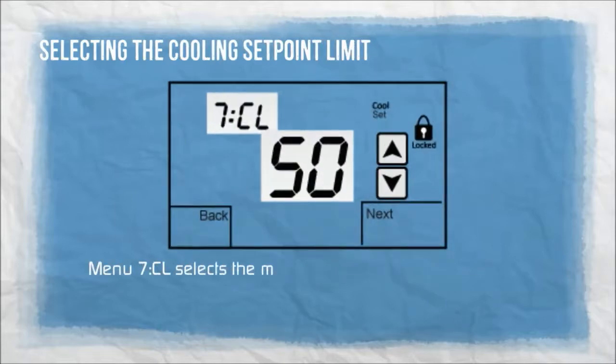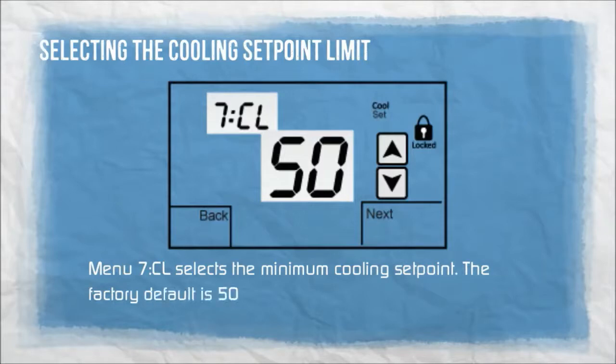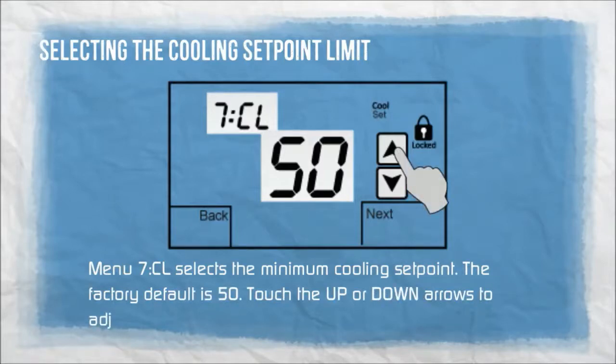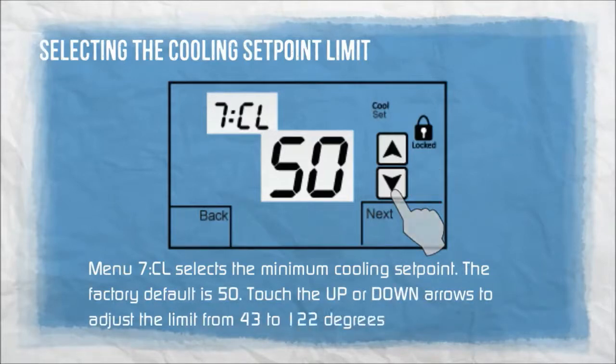Menu 7CL selects the minimum cooling set point. The factory default is 50. Touch the up or down arrows to adjust the limit from 43 to 122 degrees Fahrenheit.